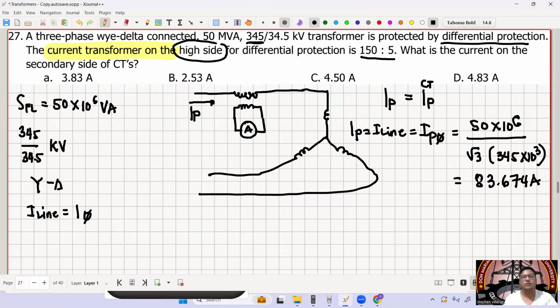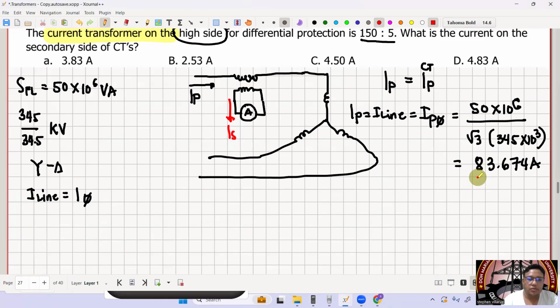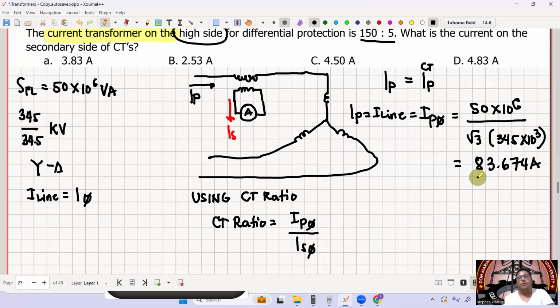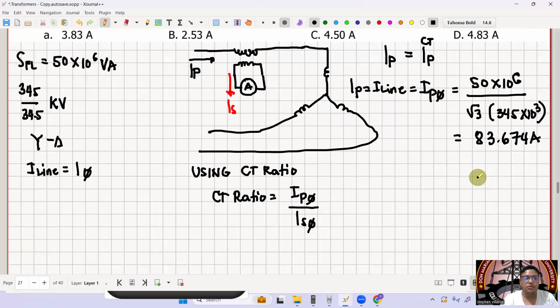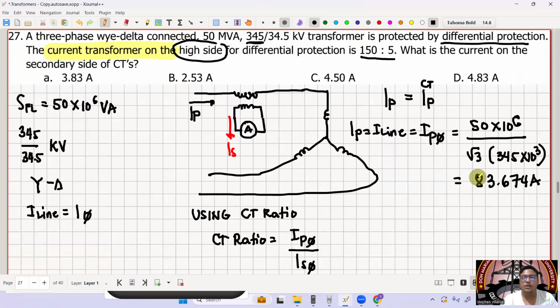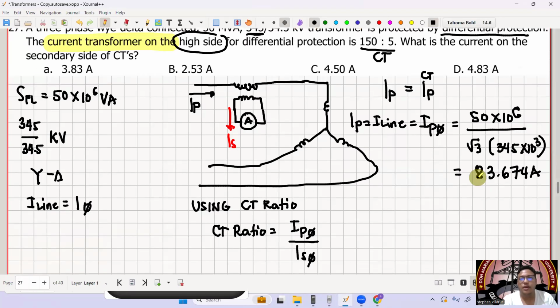So that's 83.674 amperes. Now let's go to the secondary side, IS. Using our CT ratio: the CT ratio is equal to IP per phase over IS per phase. What is our CT ratio here? That is 150 is to 5.